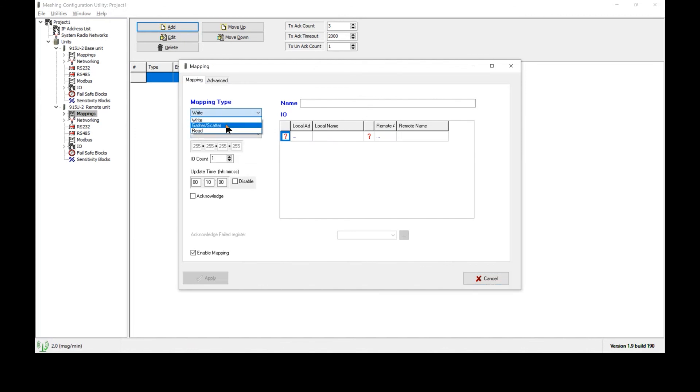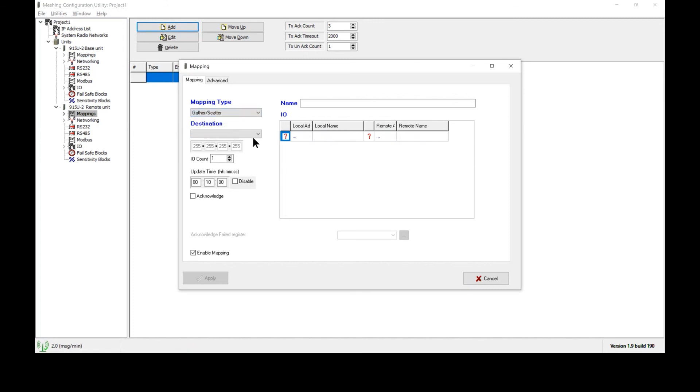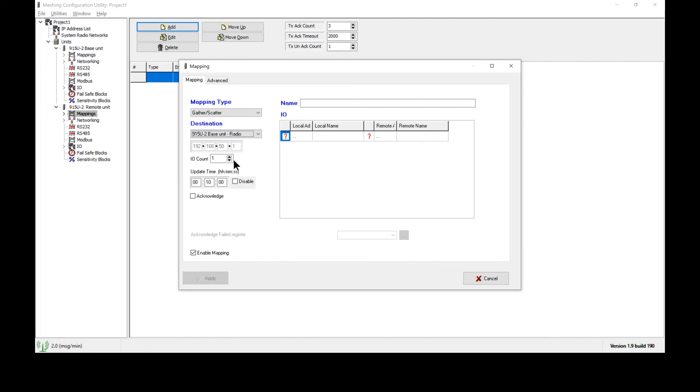We will select a gather scatter mapping to send all values at once. We also have the option of a write mapping, which can send a consecutive block of values, or we have a read mapping, which will read the values from the remote radio, in other words, sends the data in the opposite direction. We're going to use gather scatter for today's example. The destination radio here will be our base unit and selecting its radio address. The IO count we will set to a value of four. The update time we will reduce down to one minute.